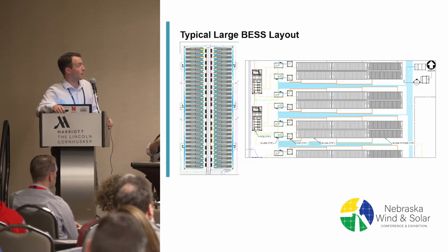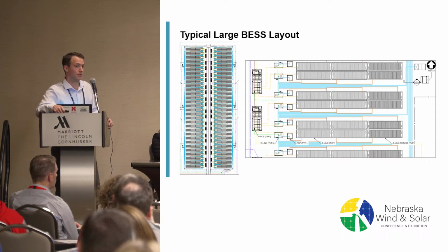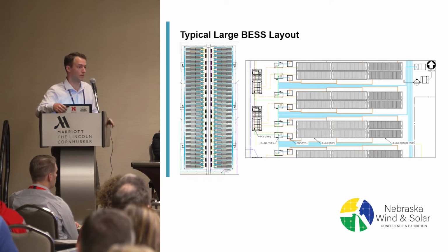So having an accurate design, thinking through how that cable and conduit is managed, making sure the appropriate de-rates are considered, and that the installation methodology is thought through sequentially to account for how much is going in the ground in a tight area, is really important.